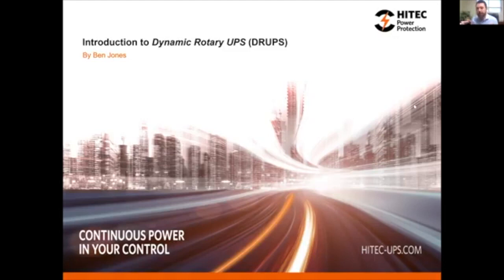Typically, if an engine doesn't start for us within 5 seconds, it's a fuel system problem, because we have redundant batteries and redundant battery starters. If you don't have fuel, it's not going to start within 10 seconds. The reason I say that is because without fuel, your diesel generator isn't going to start, and your batteries in a static UPS, as a comparison, might give you 5 minutes, but you're not going to get a diesel generator tech there to fix it. So you have 4 minutes and 50 seconds to panic. But it's a great question—that's the only thing I can think of as to why an engine wouldn't start.